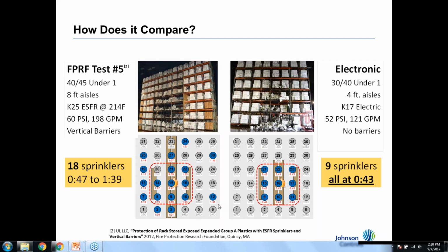So we looked at that and we said, okay, we want to control this. If you look at the right side of the slide, each one of the sprinklers inside of the ring, the 9 heads that we have picked, actually actuated all at 43 seconds. In the fire sprinkler world, you're basically creating a mini deluge system. You're allowing the fire to build, you're actuating, and you're creating a deluge just over that control area. We did it all in 43 seconds with a K17.